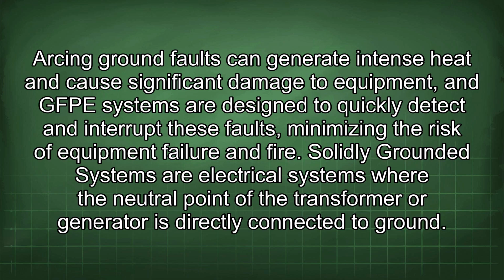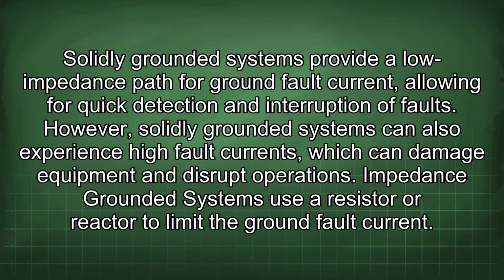Solidly grounded systems are electrical systems where the neutral point of the transformer or generator is directly connected to ground. Solidly grounded systems provide a low impedance path for ground fault current, allowing for quick detection and interruption of faults. However, solidly grounded systems can also experience high fault currents, which can damage equipment and disrupt operations.